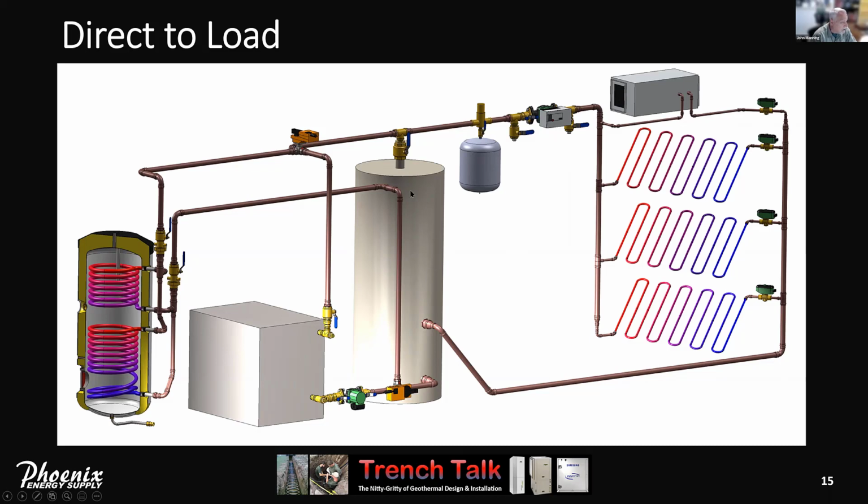Now, we can also talk about buffer tank sizing. I like it as small as possible, and it only really serves one purpose, and that is to prevent short cycling of the heat pump. Often people refer to this as storage. Well, it's not very much storage, because it can be fully depleted in about 30 minutes. So I wouldn't want to call it storage. It's simply a buffer tank to provide enough thermal mass so the heat pump does not short cycle.